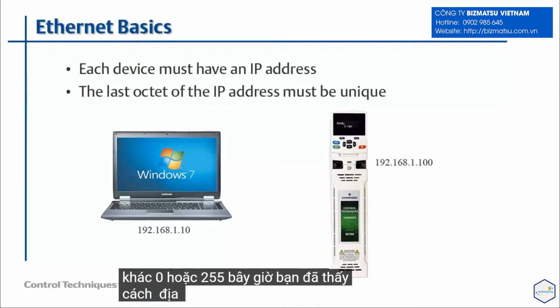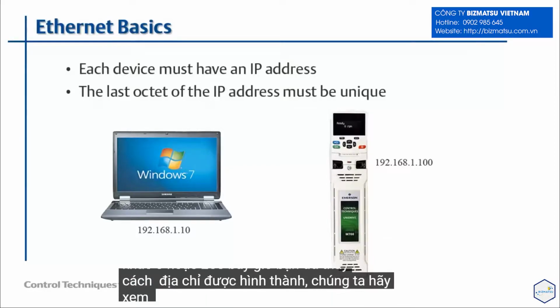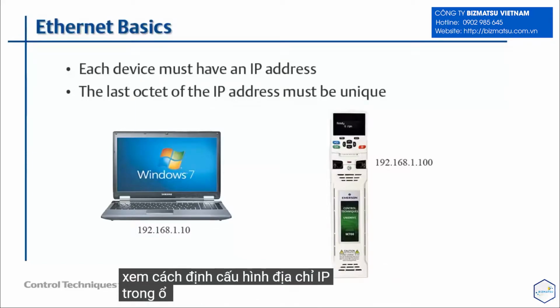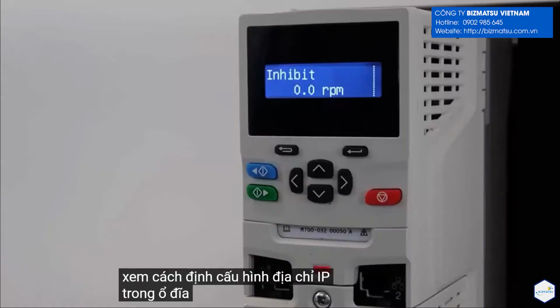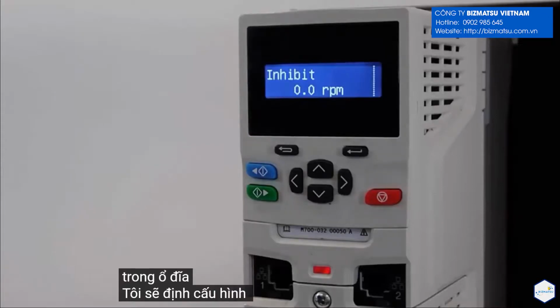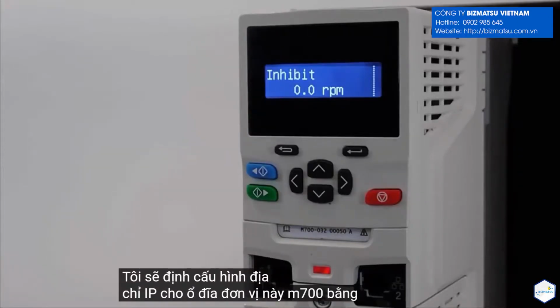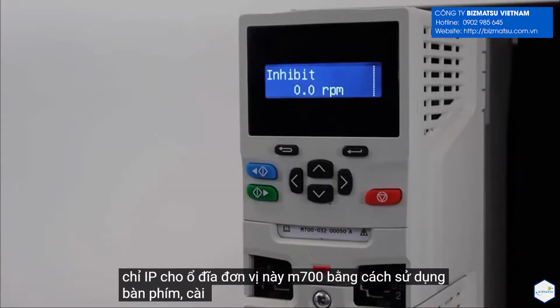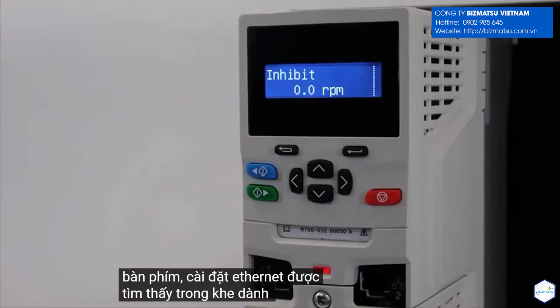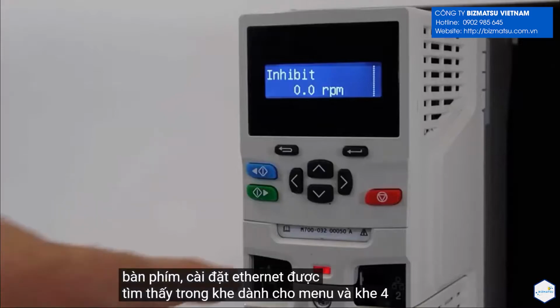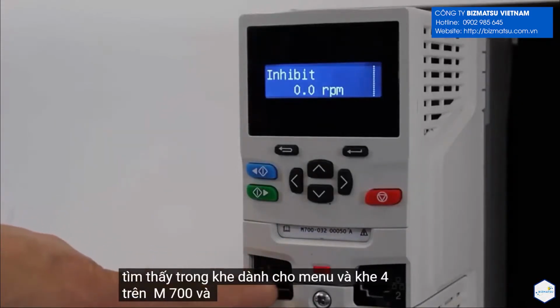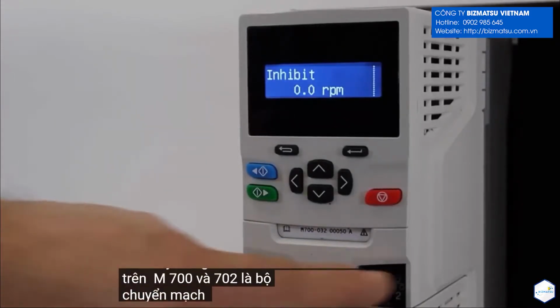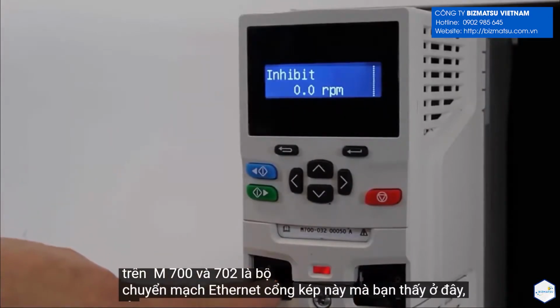Now that you've seen how addresses are formed, let's have a look at how to configure an IP address in the drive. I'm going to be configuring an IP address for this Unidrive M700 using the keypad. The Ethernet settings are found in the slot 4 menus, and slot 4 on the M700 and the 702 is this dual port Ethernet switch that you see here.